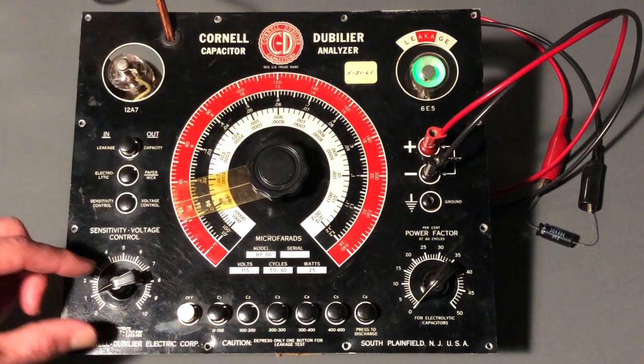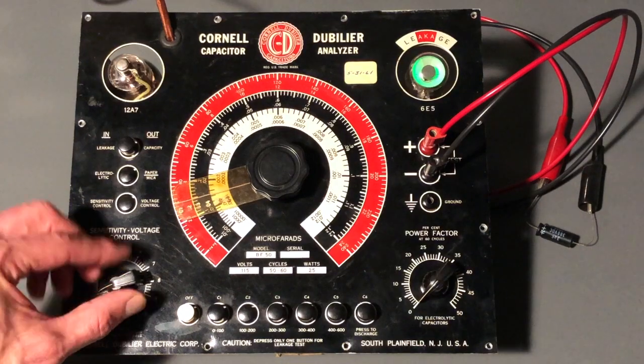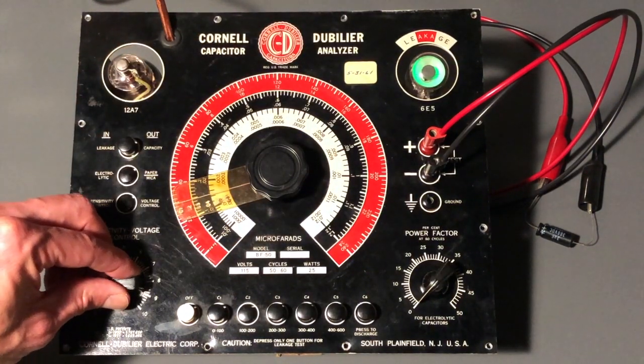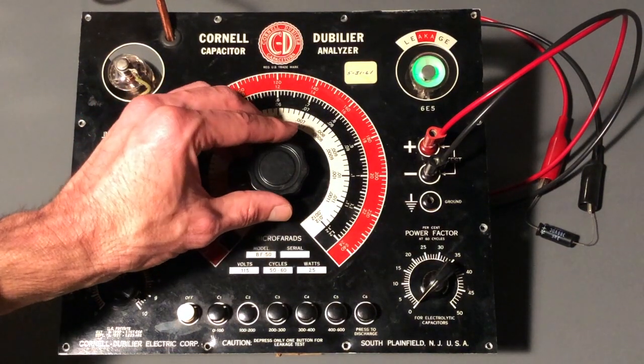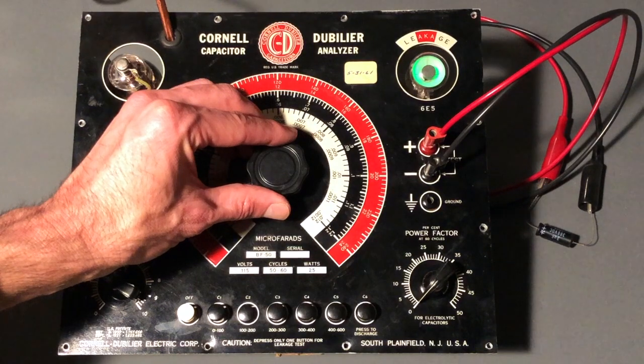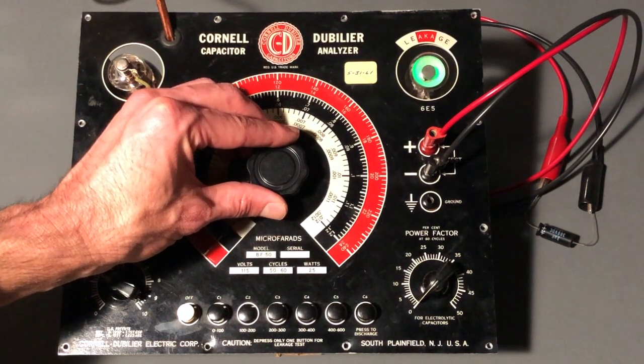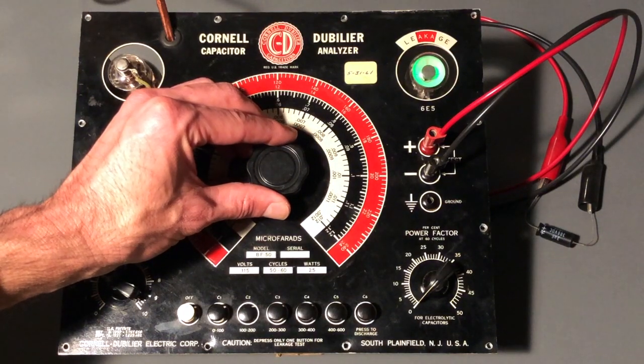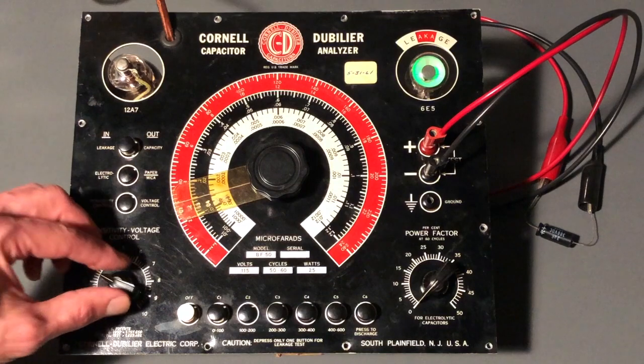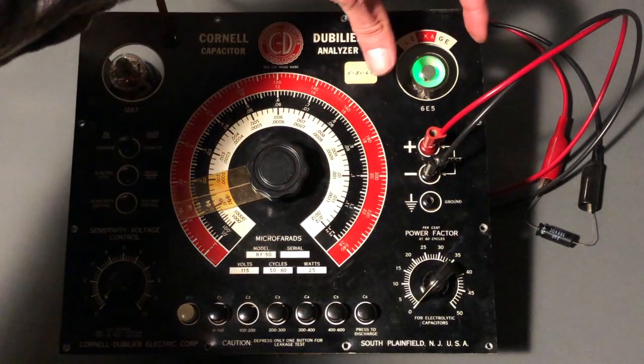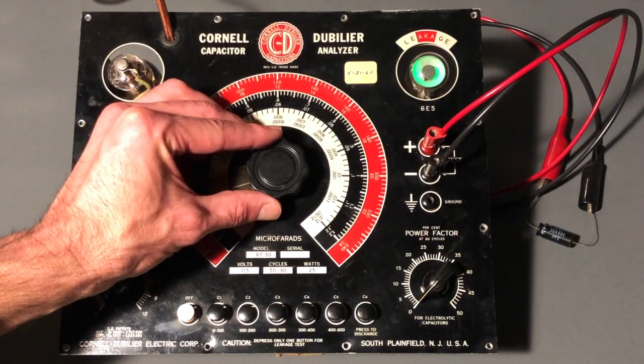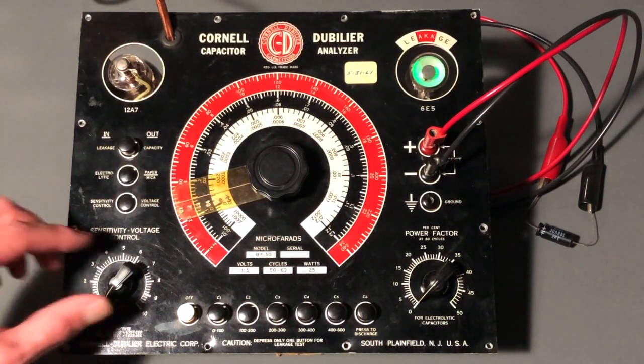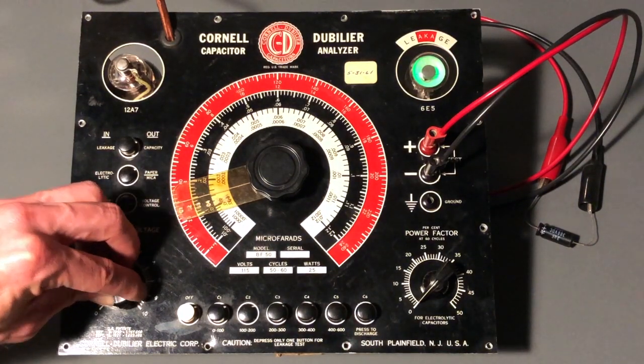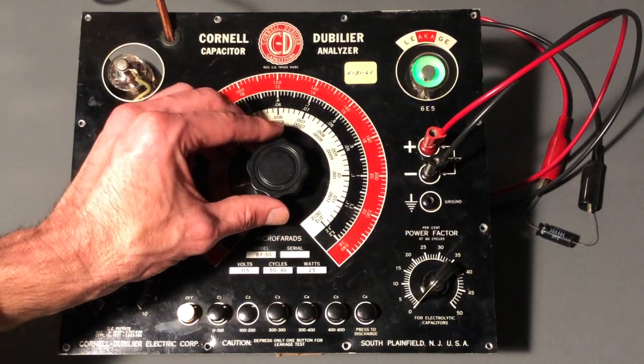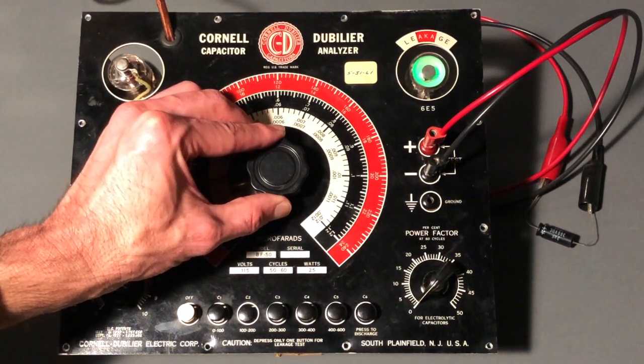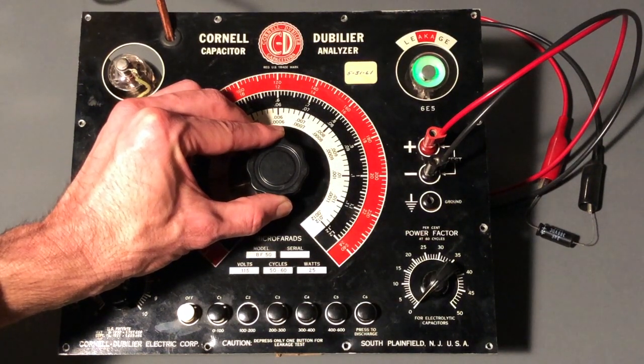Right in there. Now you can use the sensitivity control to really zero in on that, and if you turn the sensitivity up, the eye closes and it becomes more sensitive, and you can watch for the slightest change. It's very sensitive when you move this. As you can see there, the eye is completely closed. So right there is about a maximum opening. I turn the sensitivity down, you can see it opens up very wide there. Turn the sensitivity back up again. Eye basically closes all the way, and then any slight movement here will basically right there. I'll zoom the camera in.